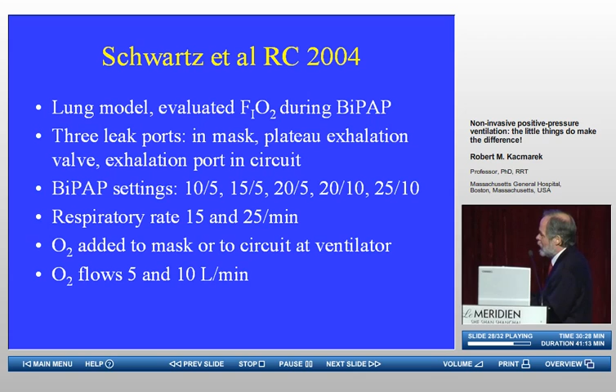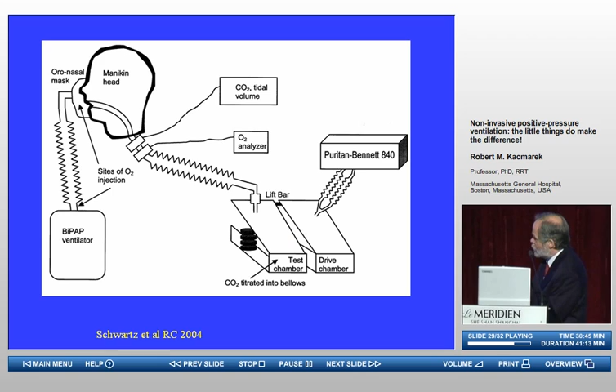So we added O2 here as it left the ventilator, or we added O2 in the mask and used a spontaneously breathing lung model to generate inspiratory effort. FiO2, as you might expect, was unaffected by the respiratory rate. We didn't have a high enough respiratory rate to overwhelm the actual flow of gas into the system. Leak port in the mask.